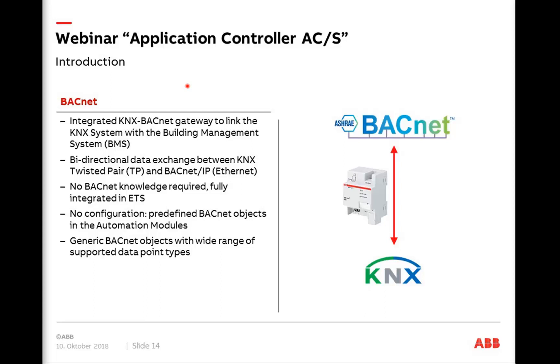A further big topic is the integration of the BACnet interface. BACnet is a protocol in building automation coming mainly from HVAC applications. There are often requirements from the market for a KNX BACnet interface, which we now provide via the application controller. We have bidirectional communication available. You simply select which data point you'd like to expose to BACnet — readable only, or both readable and writable — and then the job is done.